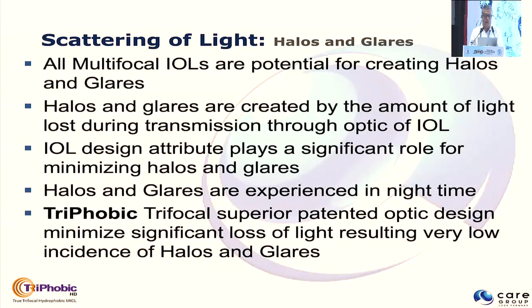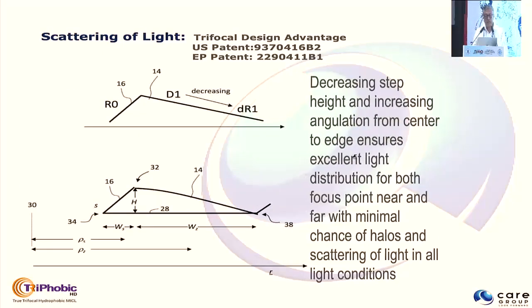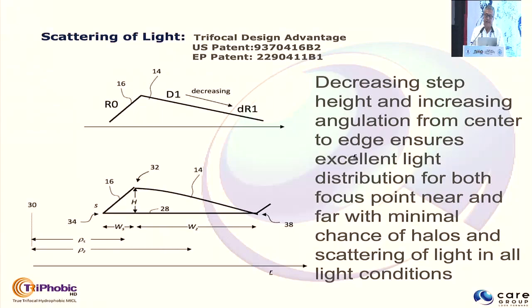As far as scattering and halos of light are concerned, all multifocal IOLs are potential for creating halos. Halos and glares are created by the amount of light that is lost. IOL design plays a significant role in minimizing halos and glares. The trifocal's superior patented optical design minimizes significant light loss, resulting in a very low incidence of halos and glares, due to its decreasing step height and increasing angulation from center to edge, ensuring excellent light distribution with minimal chance of halos and scattering in all light conditions.